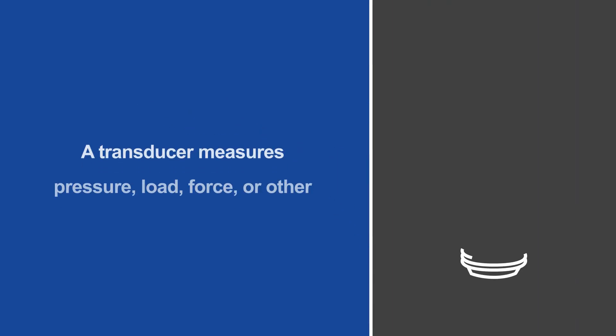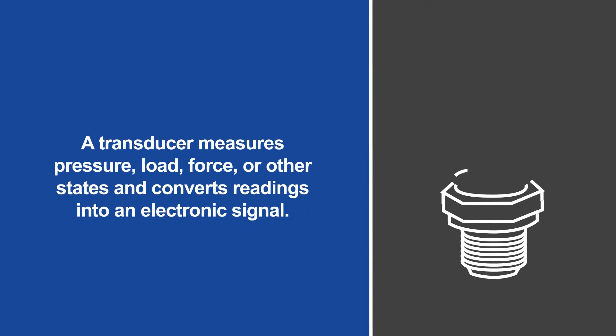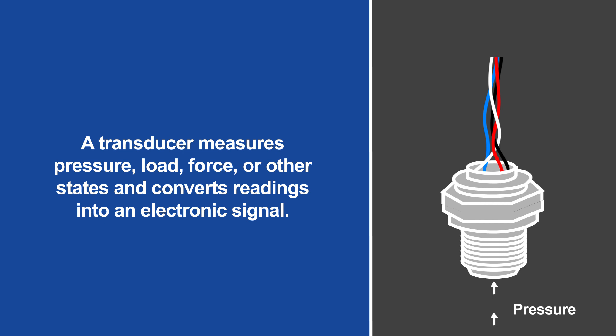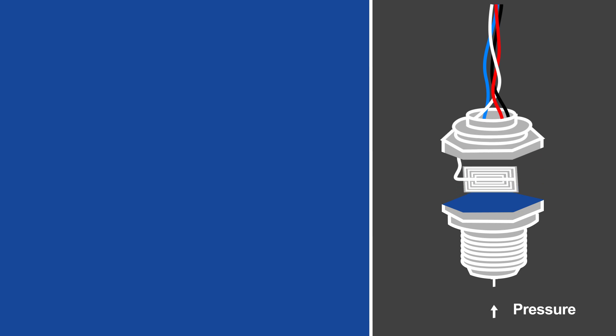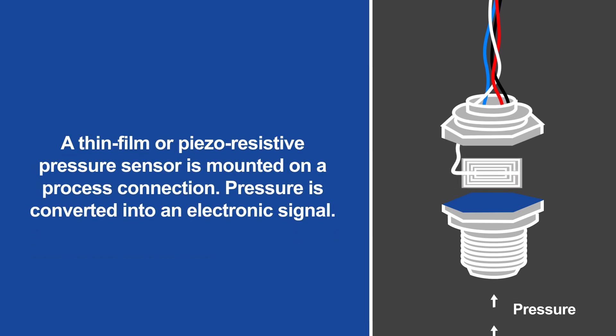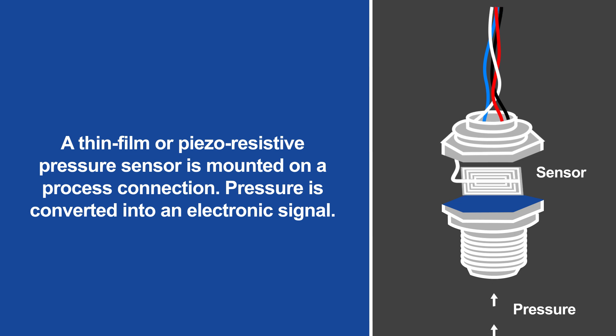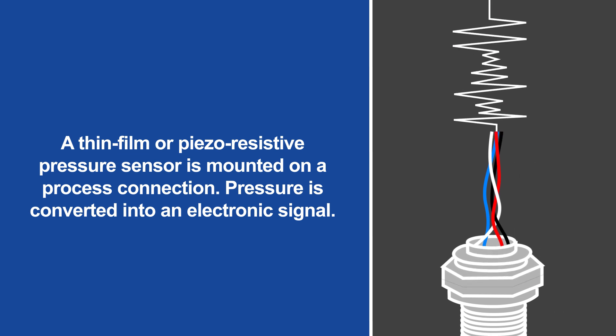Let's define these terms and then look at some examples. A transducer is an instrument that measures pressure, load, force, or other states and converts the reading into an electronic signal. In a pressure transducer, a thin film or piezo-resistive pressure sensor is mounted on a process connection. The transducer converts the pressure into an analog electronic output signal, typically as a millivolt per volt output.